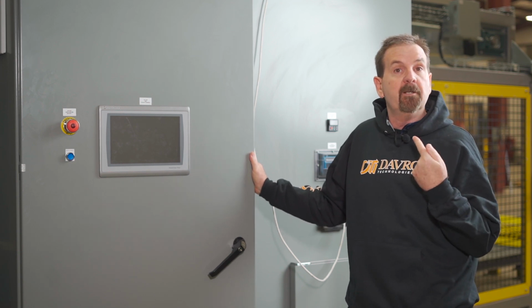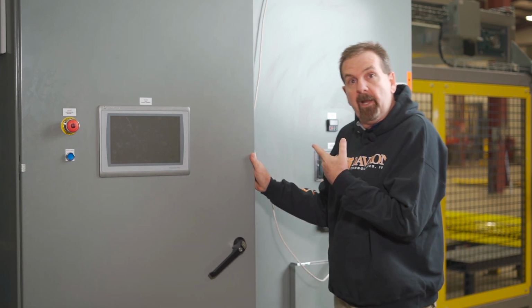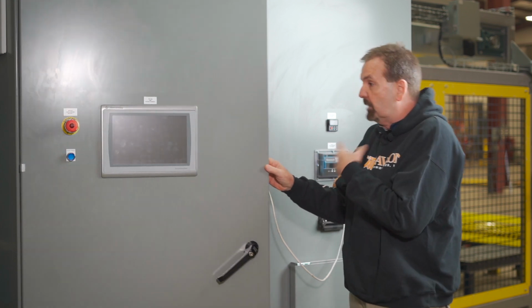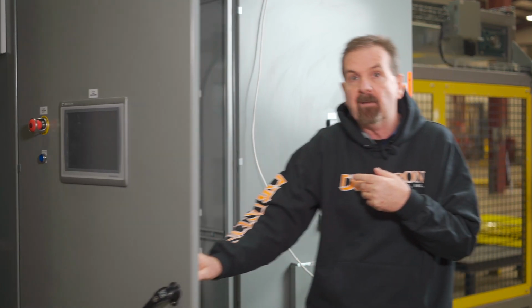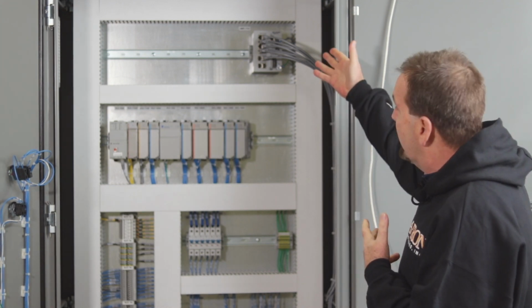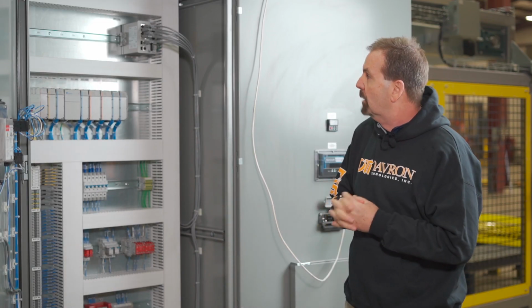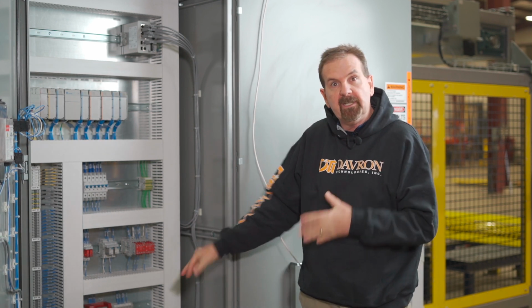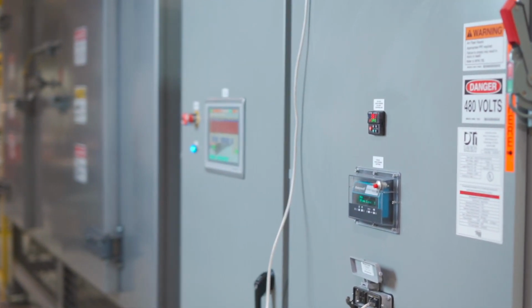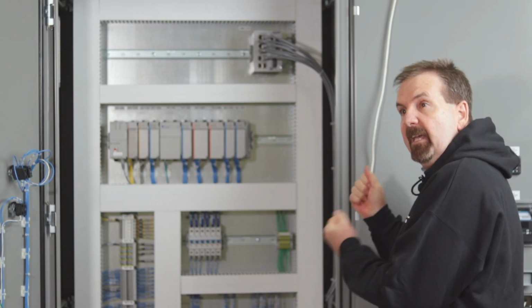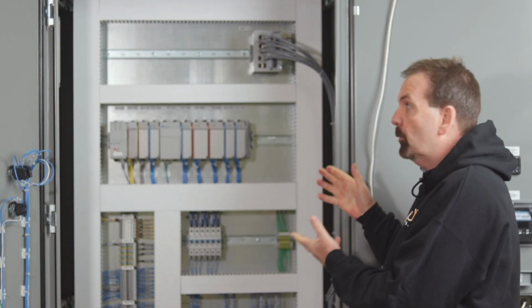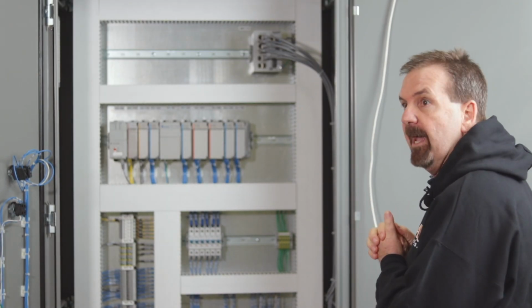One thing we've developed at Davron for our industrial control panels is separating the low voltage from the high voltage side. This is the low voltage side of the panel. With the components inside, you see we've got Ethernet switches, PLCs, input-output cards, and the safety devices - this is all low voltage. You can open it anytime, even if the machine's running or power's on, because there's no hazard or arc flash hazard.